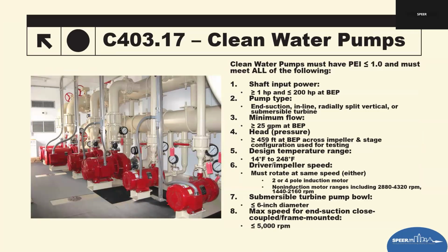One that we did see added to the 24 is what they now call a clean water pump. So C403.17 sets energy performance requirements for clean water pumps to be used in commercial buildings. These requirements ensure that pumps operate efficiently at their best efficiency point, BEP, and follow updated federal and DOE pump efficiency standards.